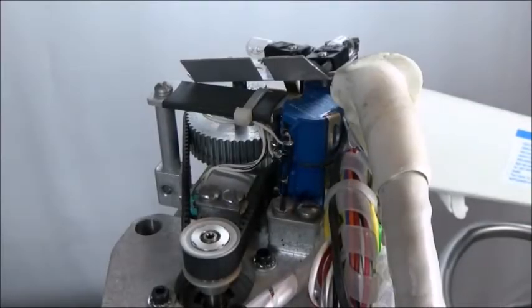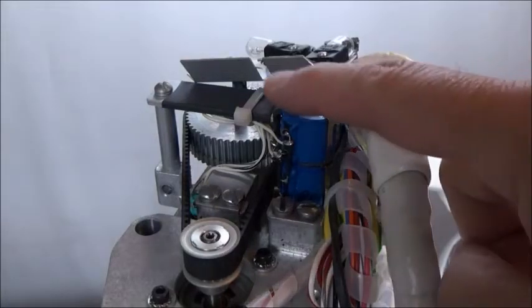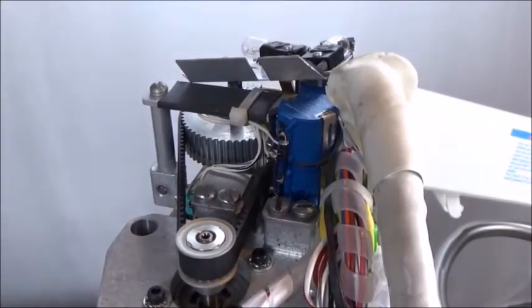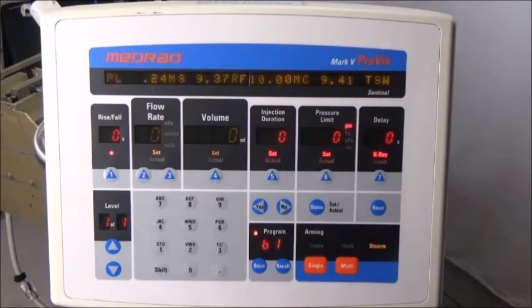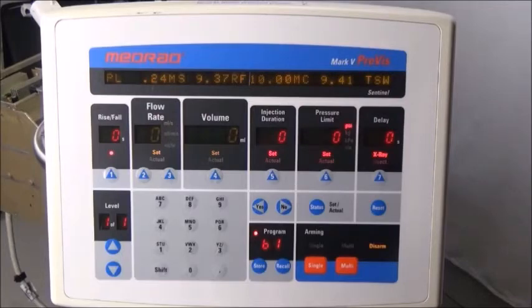This test checks, and if necessary calibrates, the R1 voltage, which is what determines the piston position. R1 is the taller of the two blue potentiometers. First, fully retract the piston, then observe the number to the right of PL, which stands for plunger, on the display. It should be 0.23, 0.24, or 0.25 volts DC.